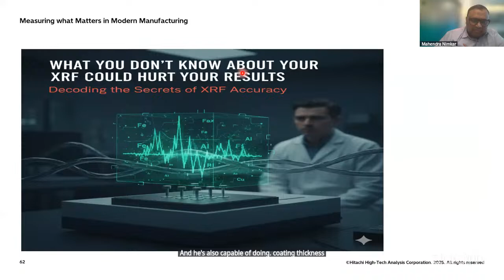I just want to mention that there are multiple types of detector. Typically, what Hitachi uses is a proportional counter and an SDD detector. Most, about 90%, of applications can be done on the proportional counter detector. Though it's old technology, 90% of the applications can be done on it in a better way. SDD is required for harder applications, as I mentioned, precious element applications or nickel phosphorus kinds of applications.